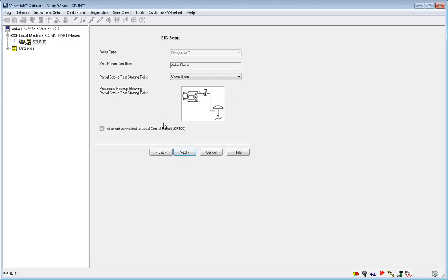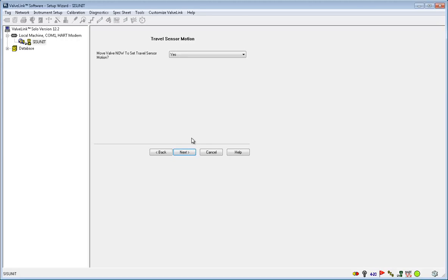Next are the SIS setup options. This is where you can choose the partial stroke test starting point. I'm going to leave the starting point for the valve as open, as this is the valve's normal position. Lastly, check the box if you have an instrument connected to the local control panel. Click Next and then select if you want to move valve now to set travel sensor motion. To avoid having to do this later, I'm going to select Yes and then click Next.